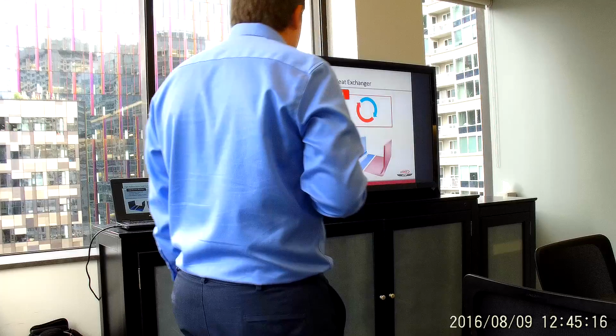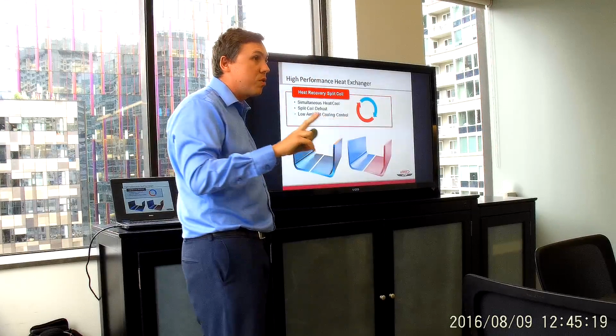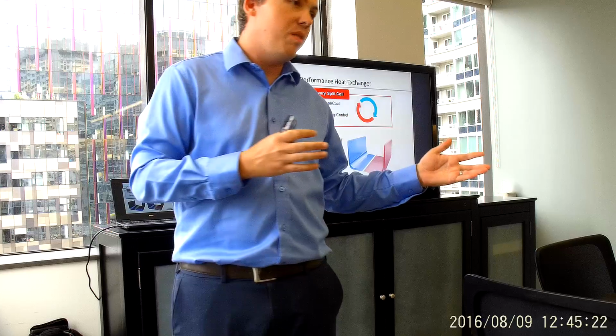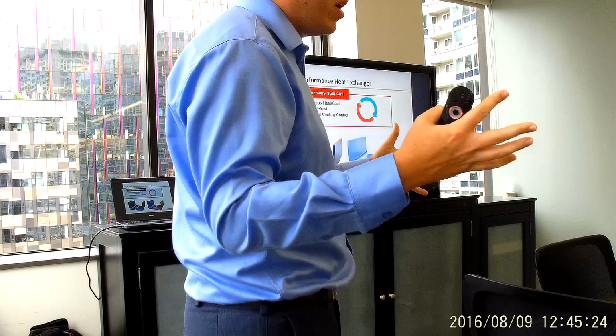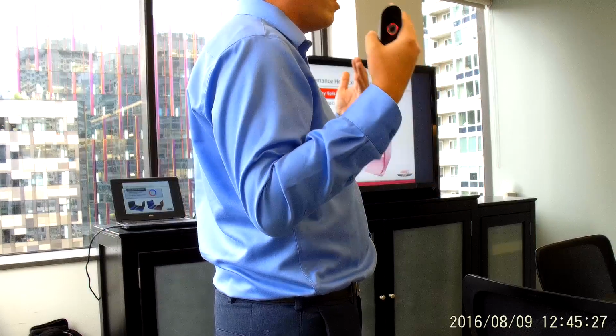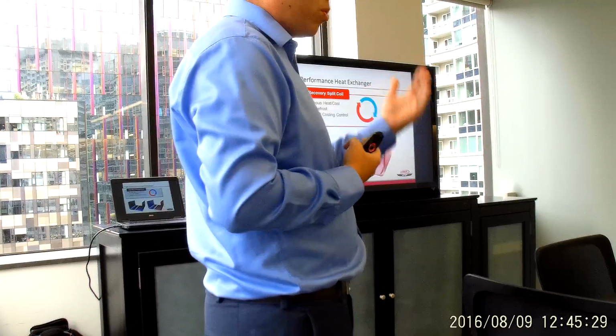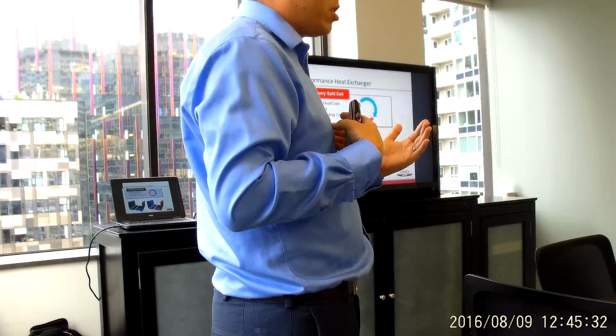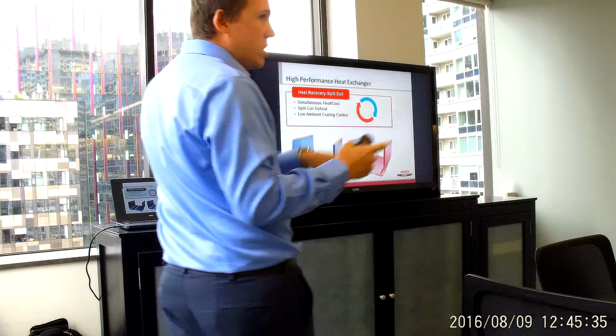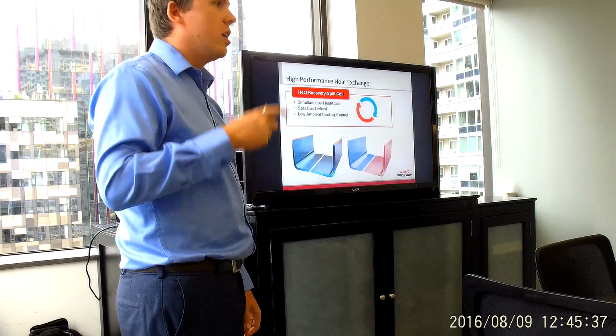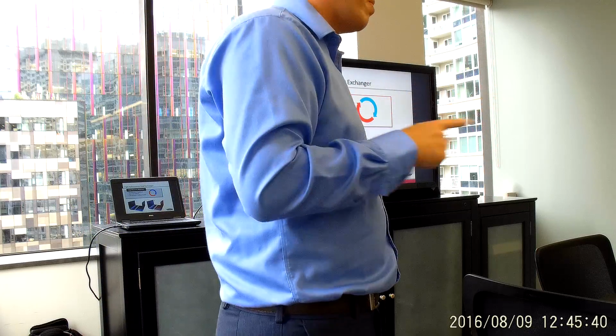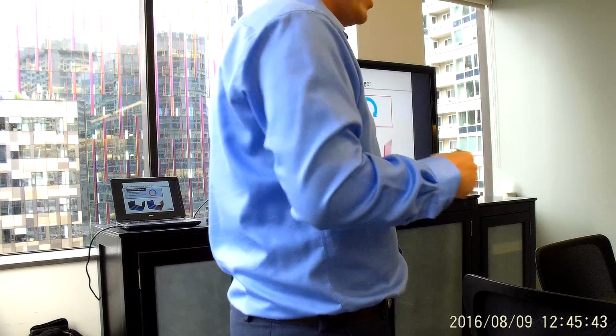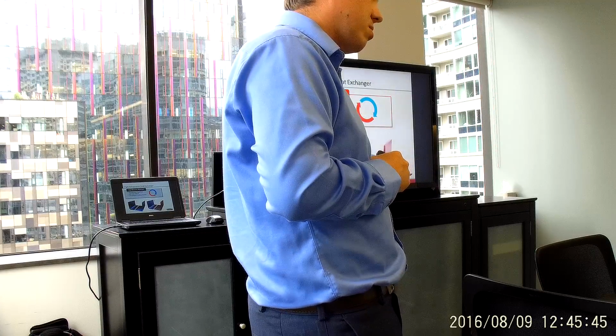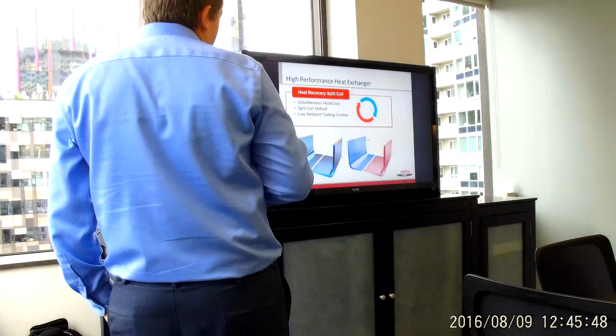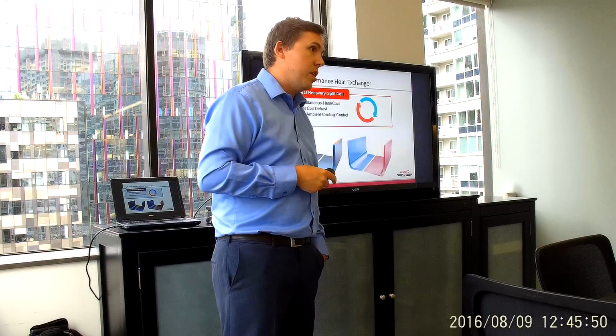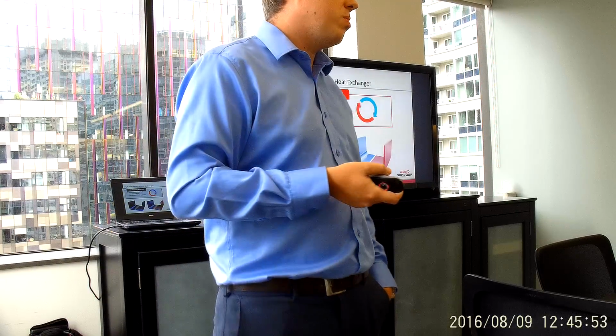Heat recovery split coil. So our coil can actually operate in 2 different modes simultaneously, which means it can be in evaporative and condensing mode at the same time. And what that allows you to do is you have independent defrost. So that unit will keep running, and then one half of the coil will defrost. Bearing in mind, if you have 3 modules of these and only one half of one coil is in defrost mode, the likelihood is you're not going to have any drop in capacity, because very rarely do you take full advantage of all 3 of your compressors on a 3-module system. And even on a single module, that'll take a defrost cycle down to 4 minutes, as opposed to some of our competitors who have a 20-minute downtime.